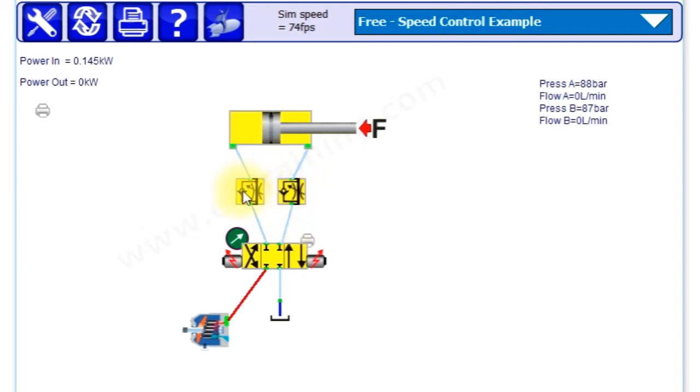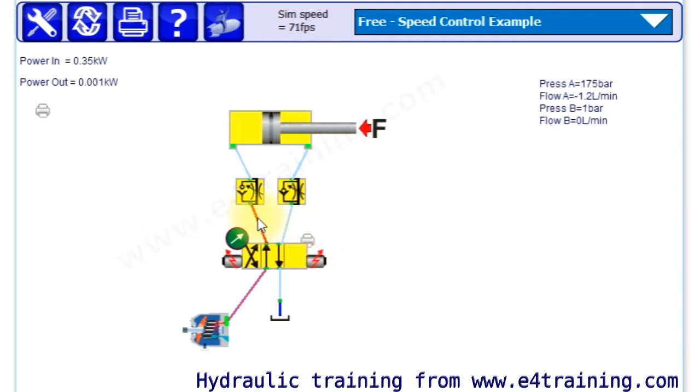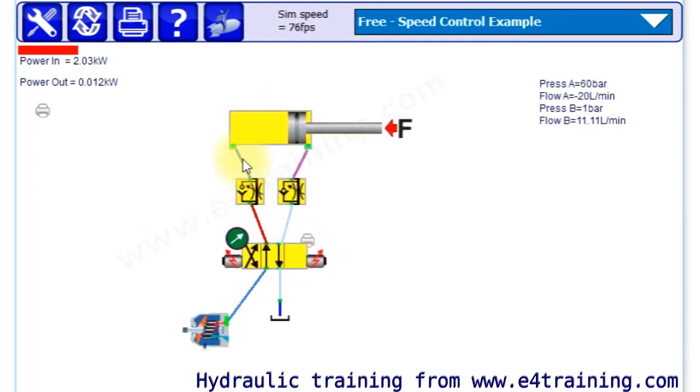flow control valves. They're meter-out, they've got a check valve that closes when the flow comes out and that meters the flow through the restrictor.